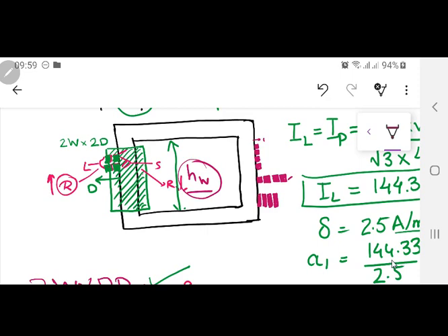Now when you are trying to talk about the height of that window, two things are there: low voltage winding and high voltage winding. You have to see how much length they cover. Now we already know that a high voltage winding, since it's going to have a lesser current, is going to have more turns because this is 11 kV, 11,000 volts. So the number of turns are certainly going to be larger, and technically it is easy to see that they are going to take a larger length over here.